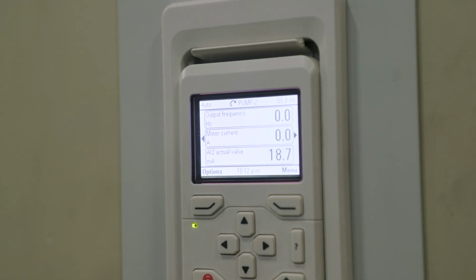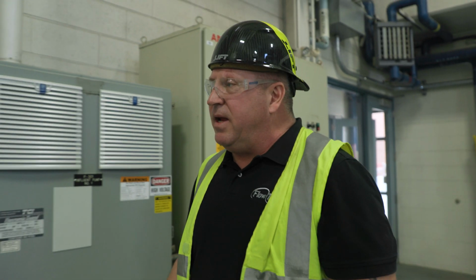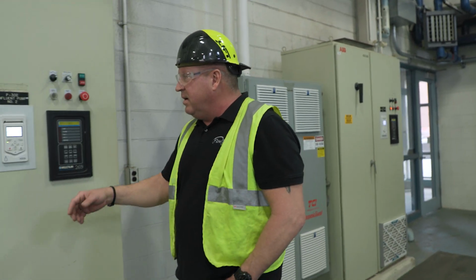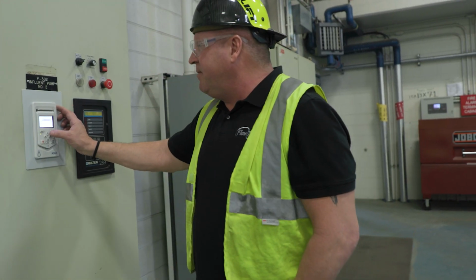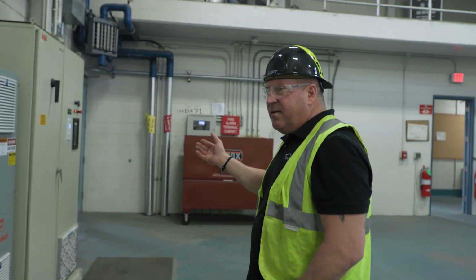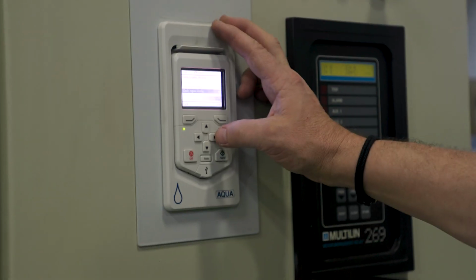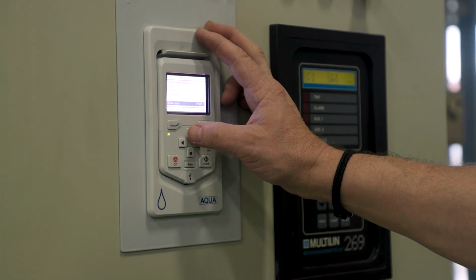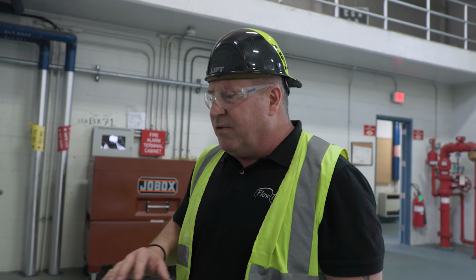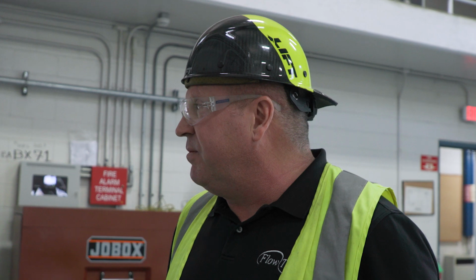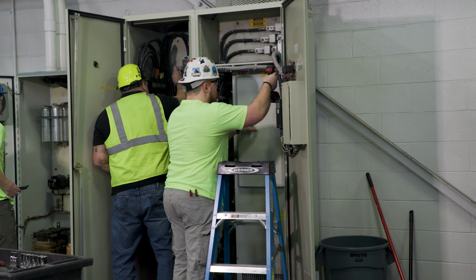What I'm going to do is use one of the keypads that I already tested, that's been wired and running, but I'm going to take this keypad out. I'm going to install it in this VFD, the new one we just retrofitted, and restore the parameters from that VFD back to this VFD. If they're all wired the same, we shouldn't have an issue. We've been successful on 3, we're on our 4th, and we should be done in a couple of days.